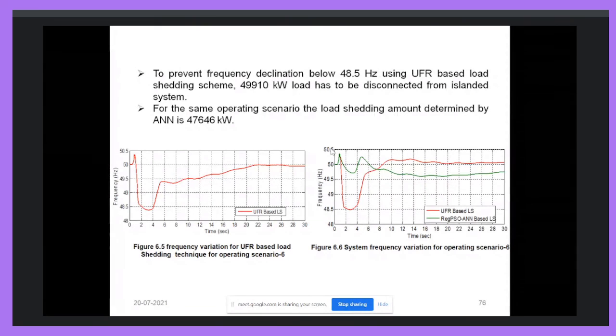Here you can see, for the same conditions, the frequency will be stable in the particular operating range. The normal operating range of the frequency is 49.5 hertz, so the frequency will be maintained in that range only.